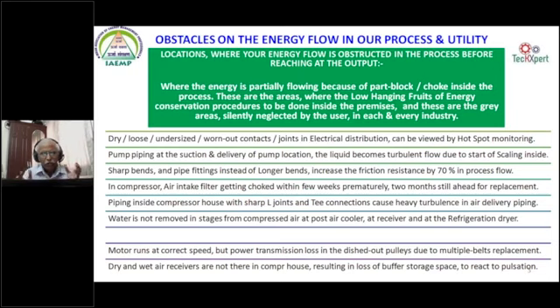Then we are seeing both the electrical side and the thermal side. On the pumping side, everyone thinks let us have an excellent 5-star rated pump, the problem is solved. It is not the solution of the pump only. It is not the problem of the pump only. It is the total pump as a system, pump and piping. If you look at it, there is ample scope on the piping side as such.